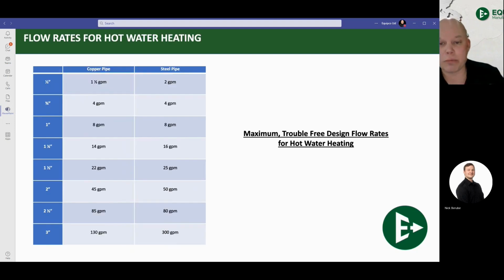You also have, and this is not my numbers here, this is put out by the Piping Institute, your maximum flow rate through piping. You have copper pipe and steel pipe. For what it's worth, copper pipe characteristics are extremely similar to that of PEX. So they're roughly the same. And you will see we have maximum GPMs that we can put through these piping systems in order to not overflow them. When we flow too fast, we cause degradation to the inside of the piping. So for example, that 1.25 inch piping that I was talking about has a max flow rate of 14 gallons per minute. The 1 inch has a max flow of 8 gallons per minute. And again, I'm talking about the copper pipe size because copper is much more common nowadays than steel. But you can see the maximum amount of flow that you can do.